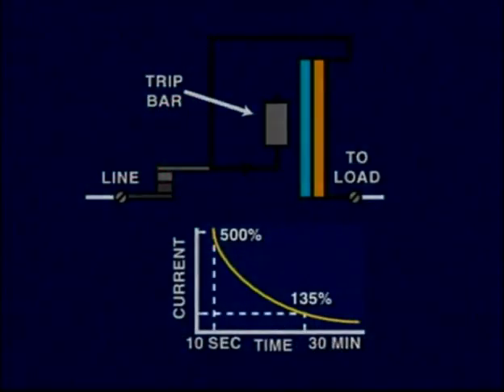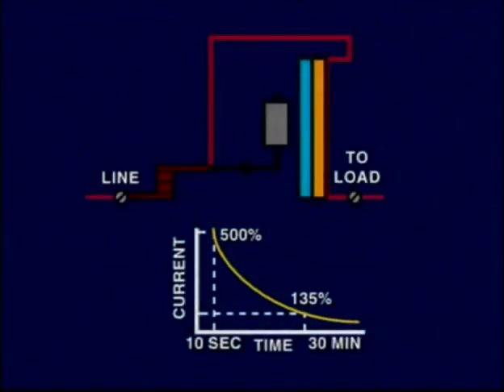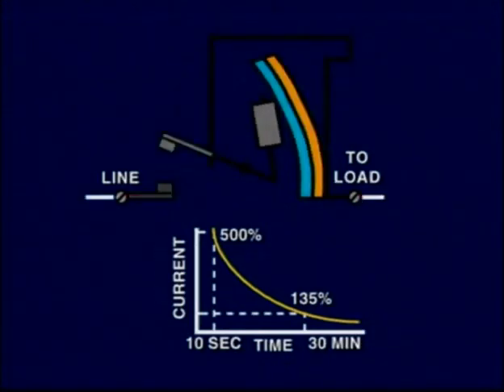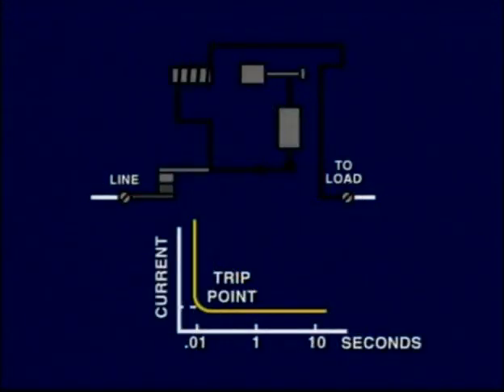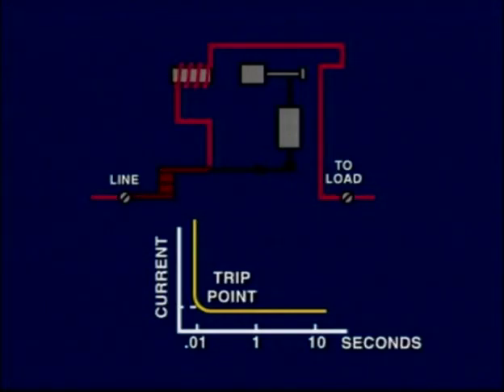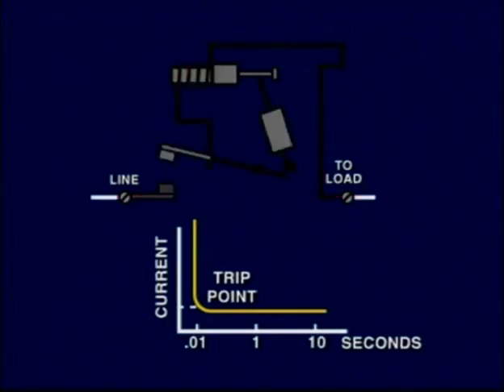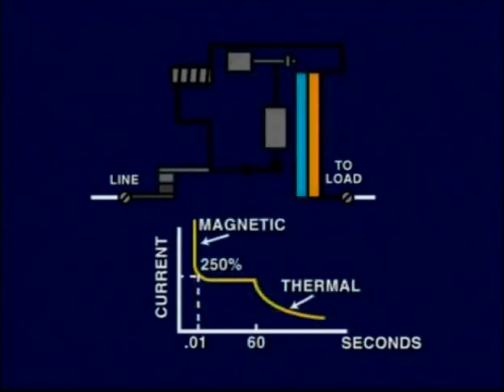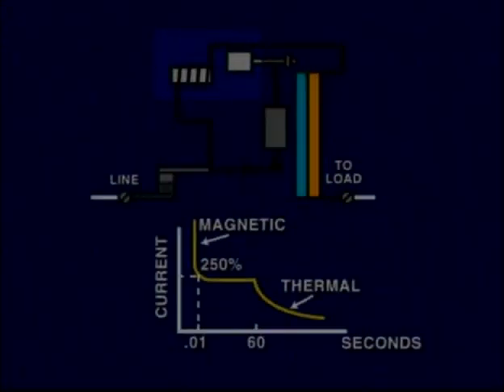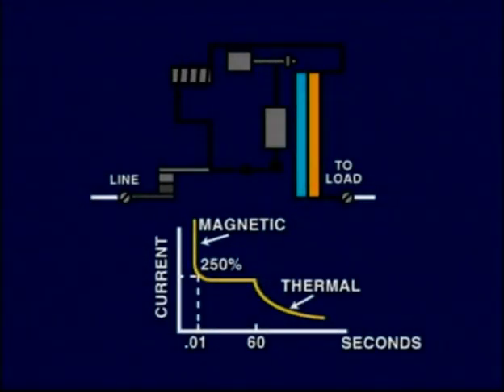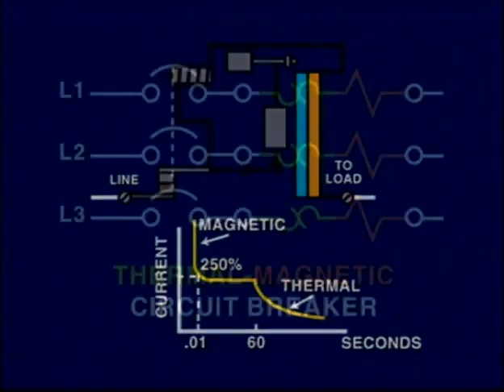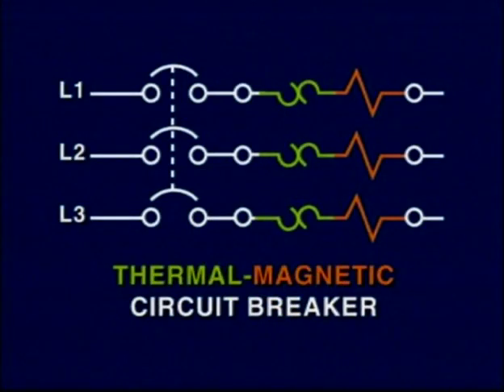The bimetal breaker responds in an inverse time manner. As the current passes, it bends the bimetal and makes it trip. The magnetic type has an electromagnet element which responds to a high current generated by a short circuit. The activation in a magnetic breaker is instantaneous. Therefore, the most desirable is the breaker with bimetal and magnetic mechanisms. One element that responds to time delay and one that responds instantaneously. These symbols represent the thermal magnetic circuit breaker. Note that one side represents the bimetal or thermal mechanism, while the other one represents the magnetic component.